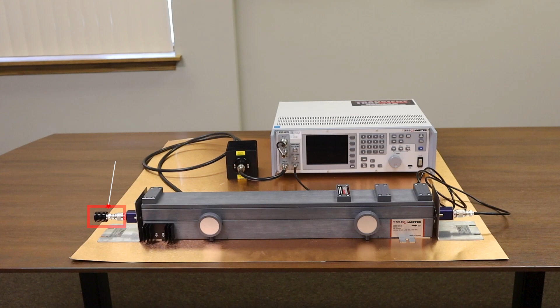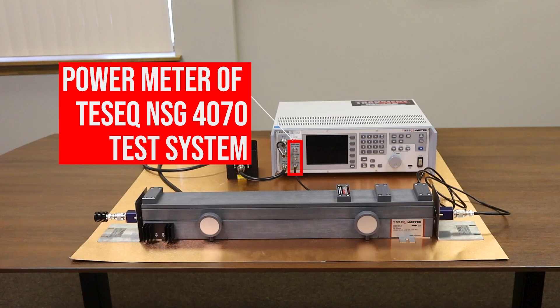Taking a look now, on the left side of our clamp, we have our 50 ohm termination load connected to our CAL 801A 100 ohm adapter. We have that adapter connected to the rod, which is going through the KEMZ 801A. On the right side of our KEMZ 801A, we have our other 100 ohm CAL 801A adapter, and then we have that connected to our channel 1 power meter on our TESEQ NSG 4070 test system. While the models of equipment may vary slightly between different manufacturers, the calibration setup will remain generally the same. Keep in mind, for these conducted RF immunity tests, grounding is especially important, so it's crucial that those adapters have good connections to the ground plane.